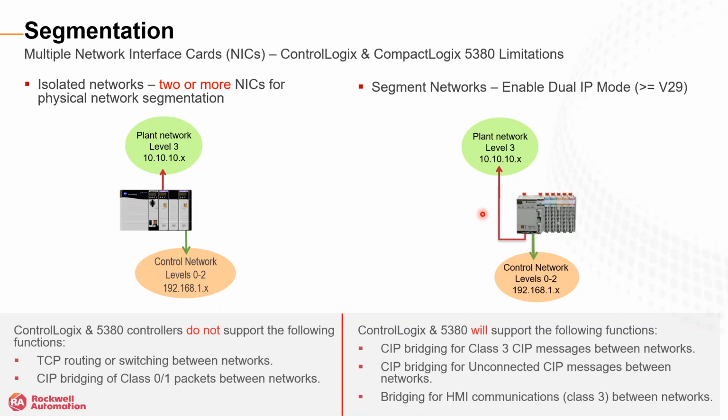So we do have the ability to split the ports on this. It can either support DLR as a whole, which means that port would be basically one IP address with an unmanaged switch attached to it, or split it to two separate networks. That is how we're doing the network segmentation in this dual IP mode.